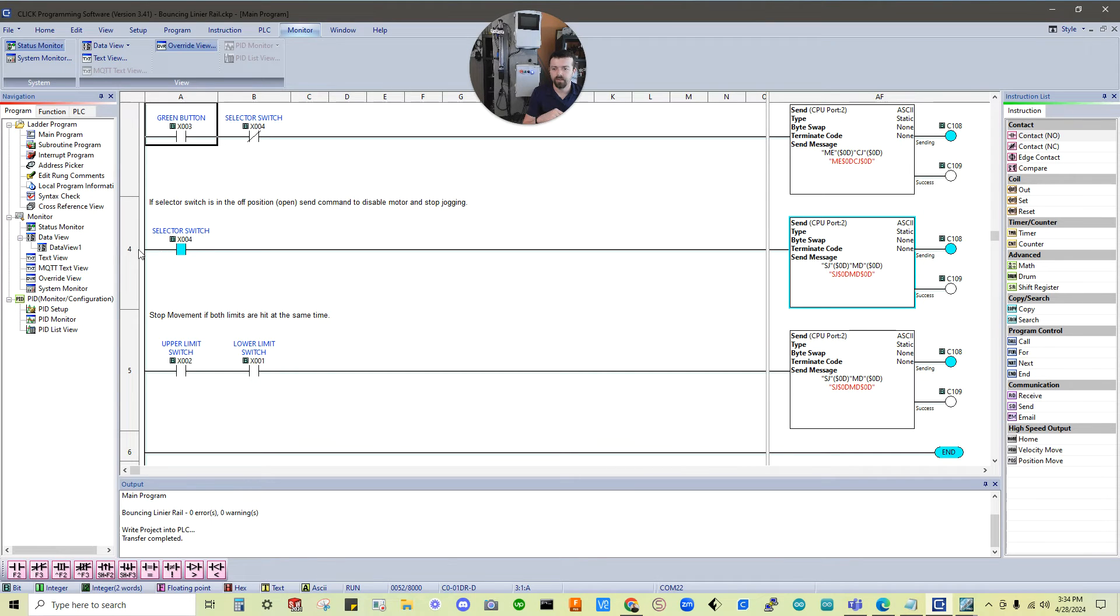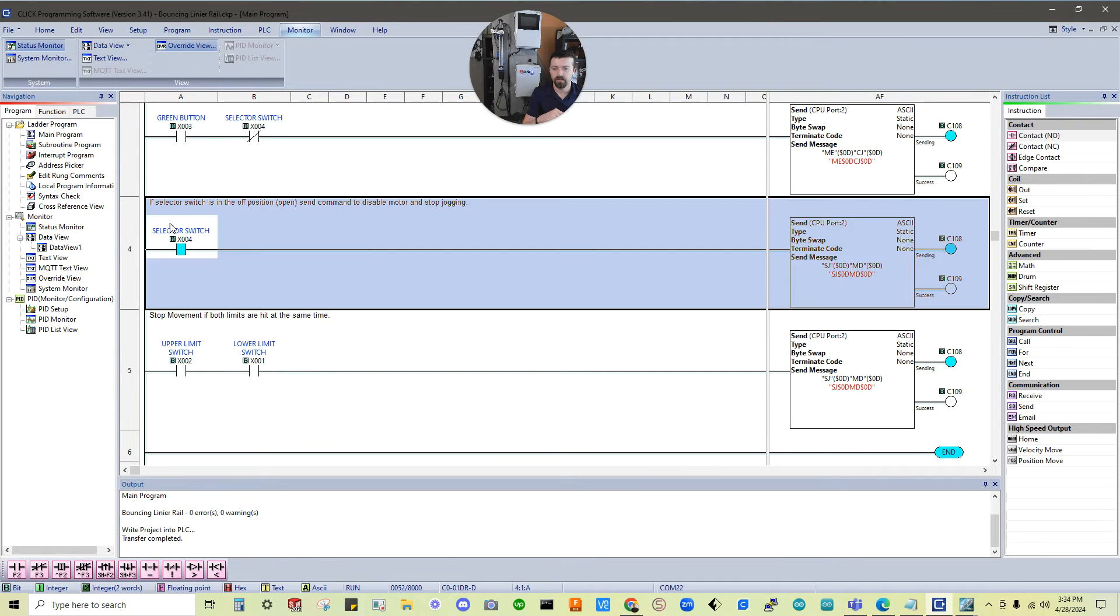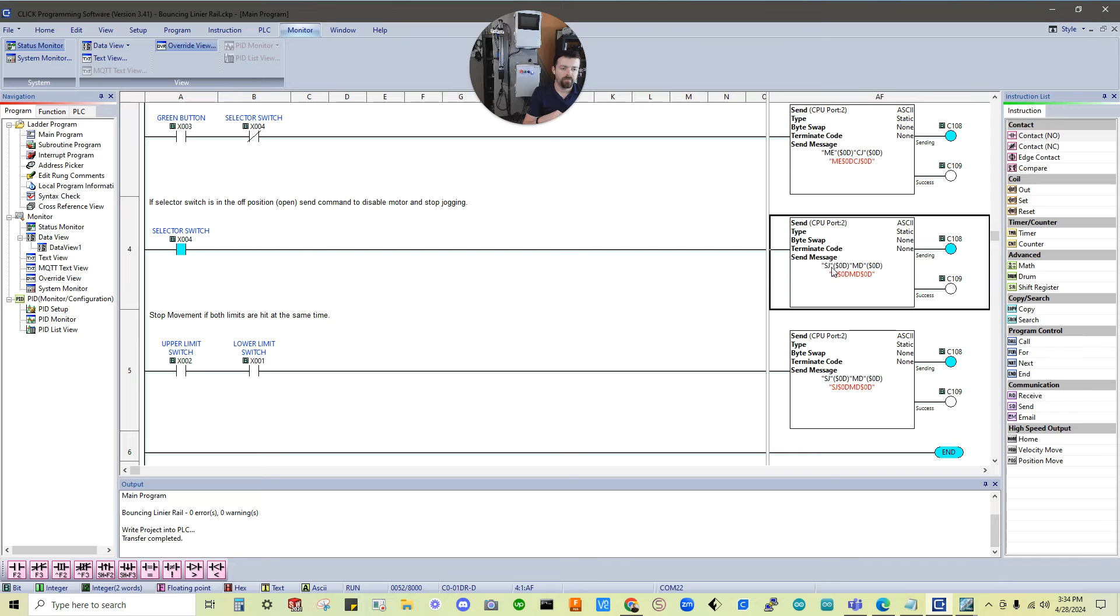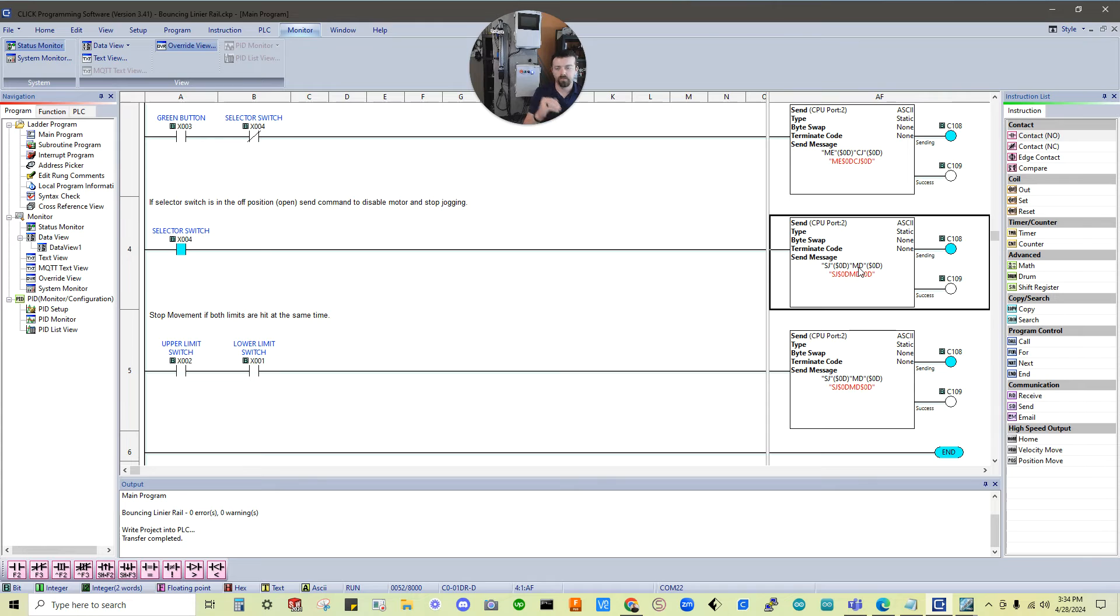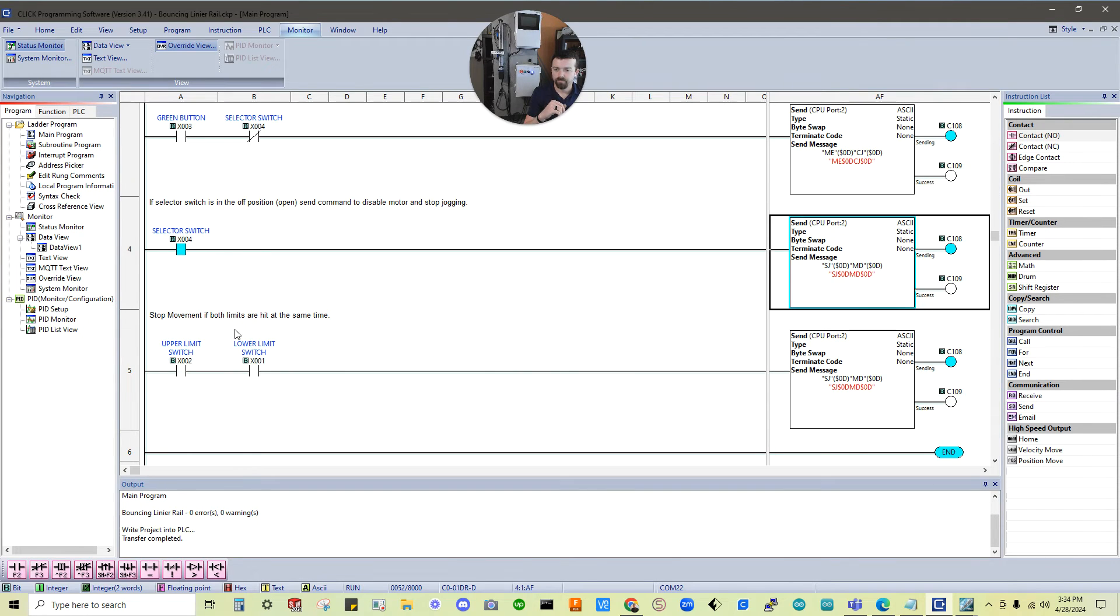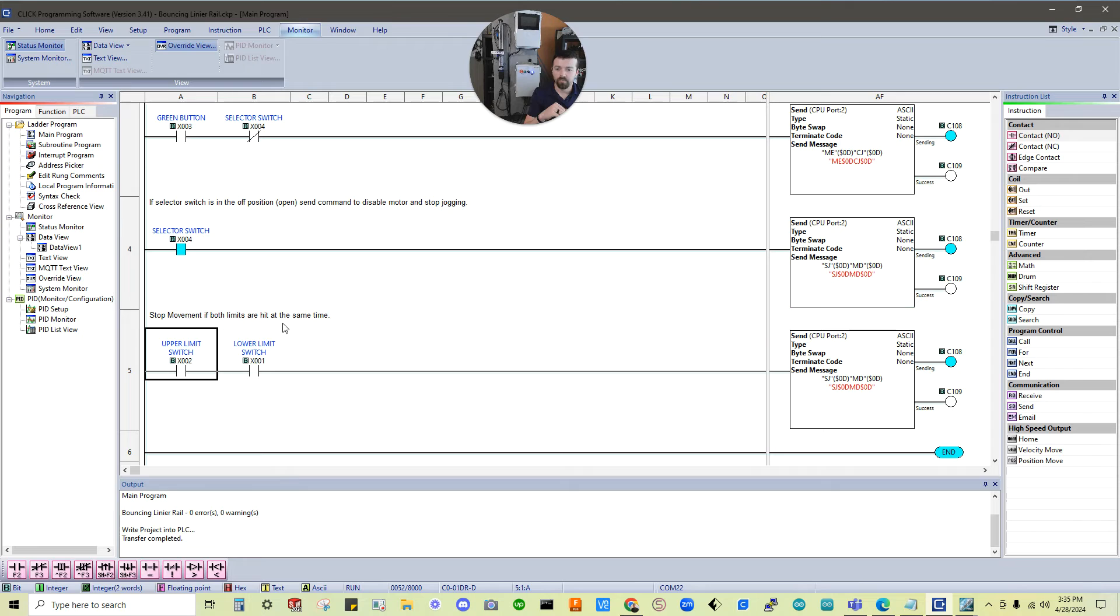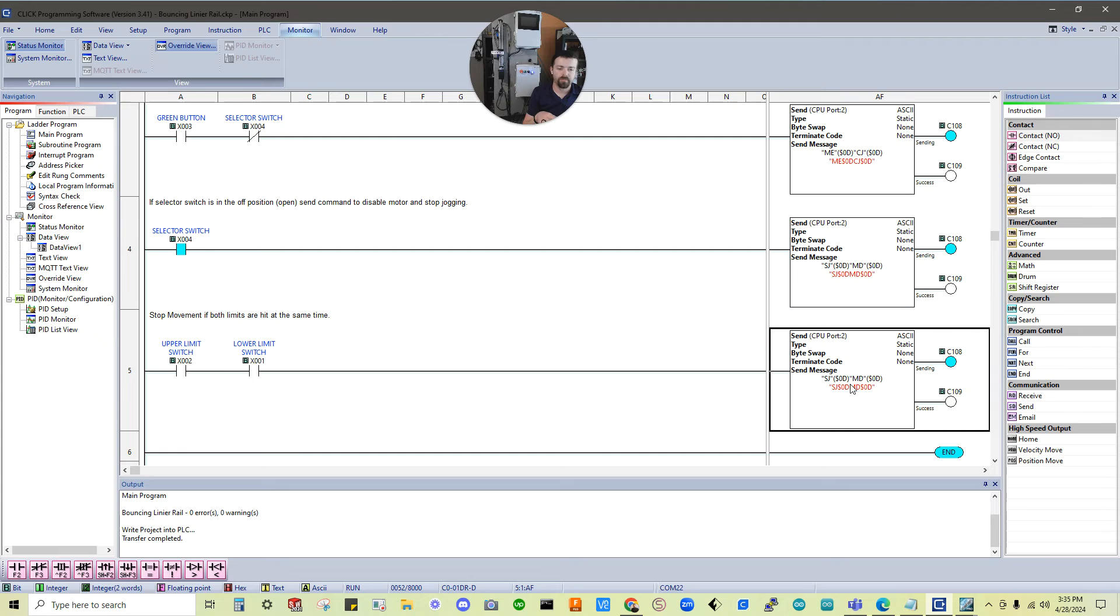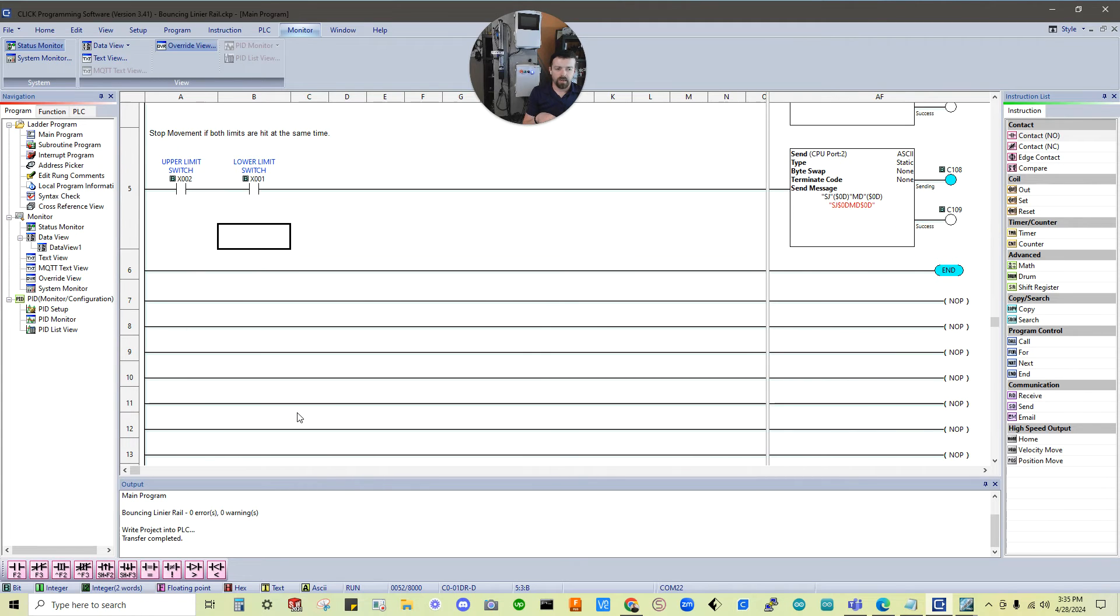Any other stuff? So we have this rung here, that if the selector switch was in the off position, open, it's going to continuously send this command of sj, which is stop jog, and then md, which is motor disabled. So let's see. If it was moving, again, we'll start it, and then it changes, and now it's not moving. This will make sure that switch overrides. So that's great. And you know, it stops the movement. Then you have stop movement if both limits are hit since that's just a safety that, hey, that should never happen. They should never both be hit. Which, if they're both hit, it would do the same thing. It would stop jog and motor disable. Okay.